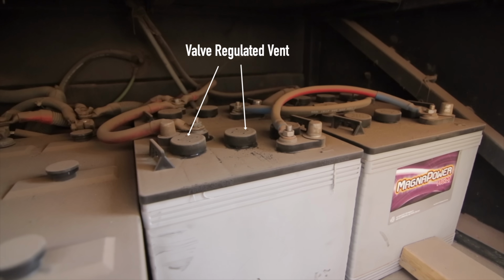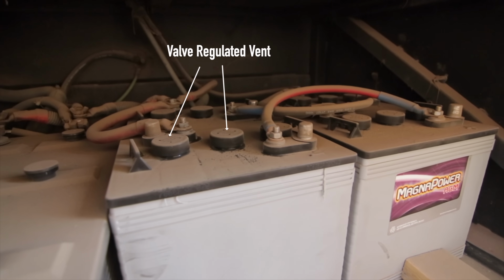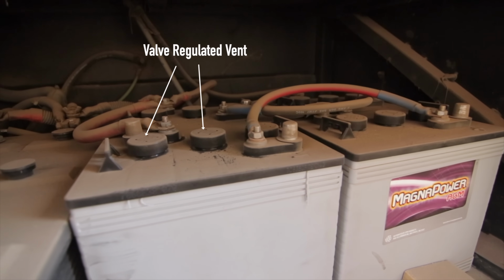So vented compartments are an absolute must for lead acid batteries. And there's actually a myth about AGM batteries that you don't need to vent them. They actually do have a valve on there. They are a sealed battery, so it's not like you're having to refill the fluid in there, and they're not venting all the time like you would have on a traditional lead acid battery, but they do have a valve in there. So if they get overcharged or some other kind of circumstance where it needs to release some of that pressure that happens inside of there, they still need to be vented.